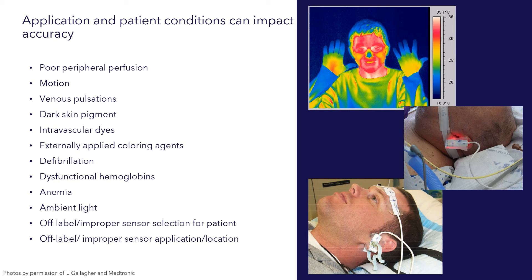Venous pulsation, while normally not occurring, can occur in situations such as tricuspid regurgitation, patients that are on continuous renal replacement therapy, and even if a sensor is taped too tight, where venous pulsation can occur and confound the arterial pulsation, creating an artificially low oxygen saturation reading.